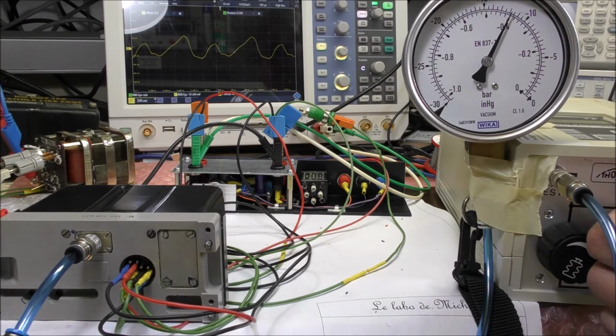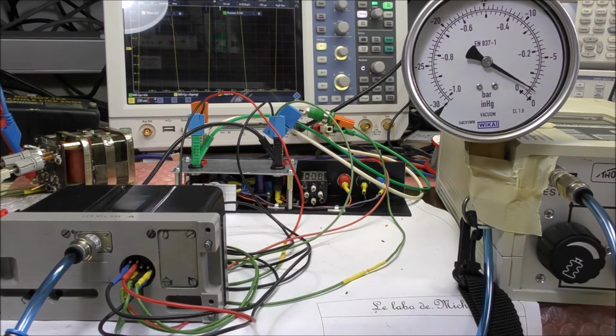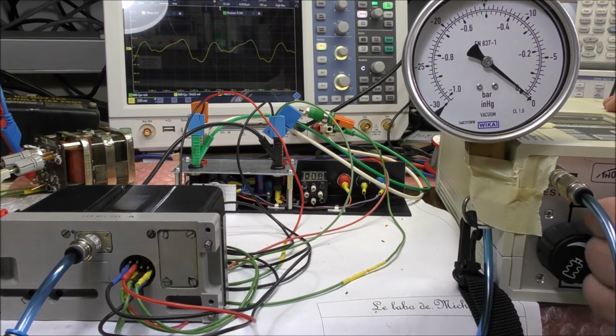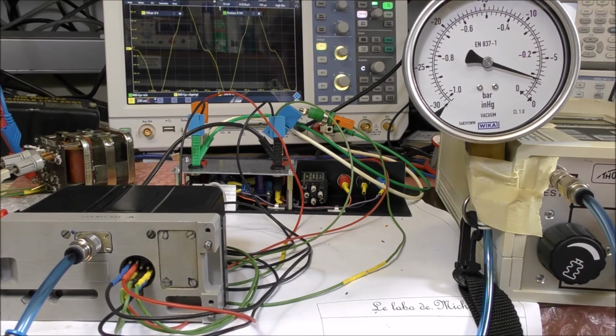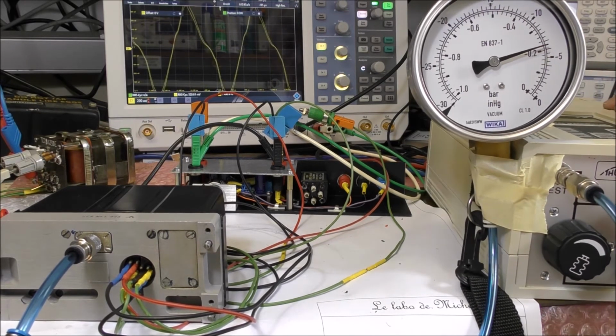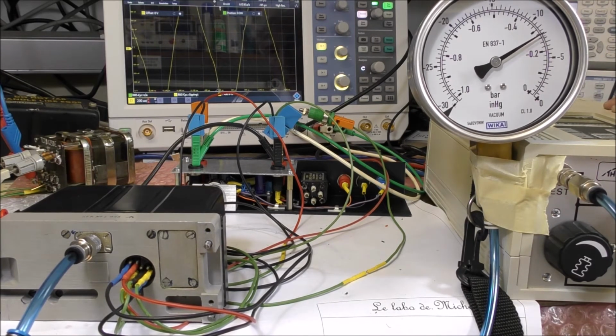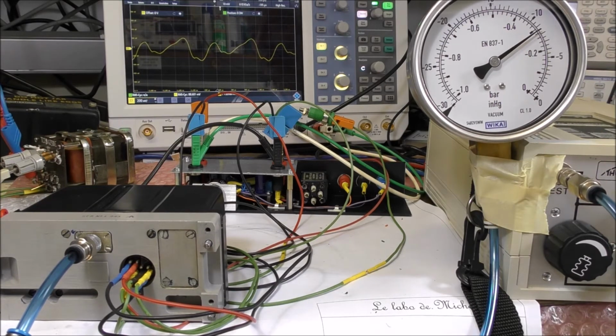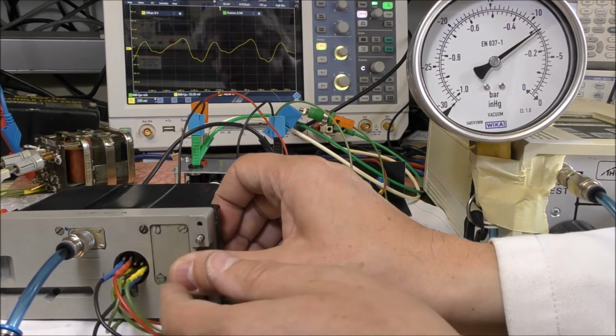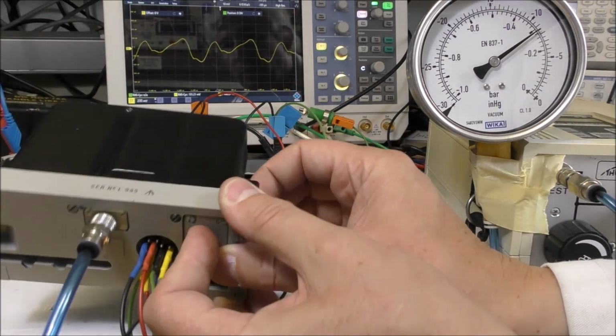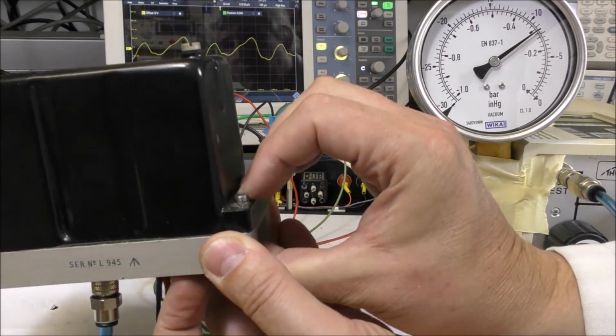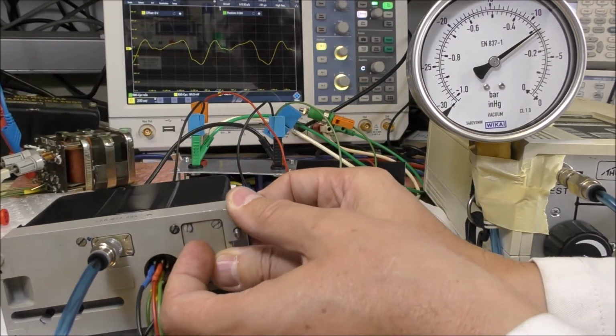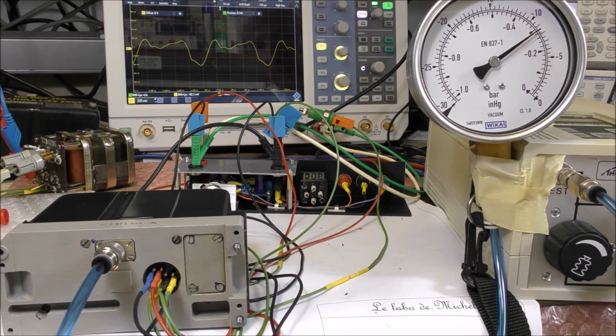You can decrease the pressure. So normally the transducer is expected to be used vertically, so we can see if there is a change in the regulation. It's more or less insensitive. There is a very little change, you can see, but it's more or less identical. So now we can test the relative mode.